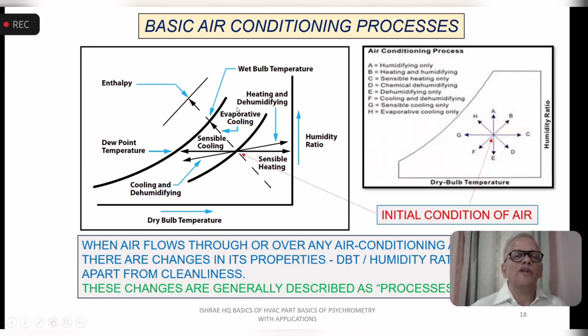Then you have evaporative cooling, which goes along the wet bulb line. That is the wet bulb temperature. As the efficiency is higher, you achieve higher relative humidity, and there is a conversion from sensible heat to latent heat. So the enthalpy level doesn't change, but you are increasing the relative humidity, and there is a decrease in dry bulb temperature. So these are basically the processes.